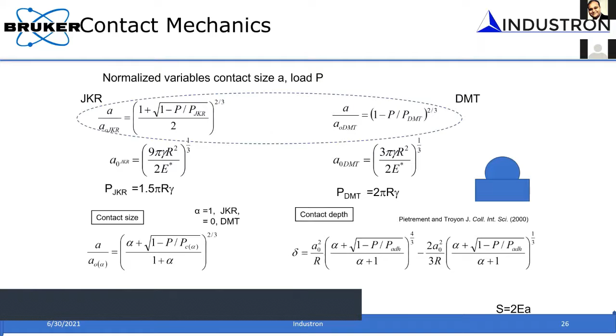So we call it the BioSoft bioindenter, which is basically a transducer capable of applying very small forces with high force sensitivity, but also has a very large displacement range. It has the same elements, for example the capacitance sensor normally used in our typical high-strength transducer, and you still have that, but it is used in combination with a flexure actuator and an additional sensor, so you can go to a very large displacement range, about 150 micron, while keeping the same force sensitivity that we have with the normal transducer that we use in our 950.